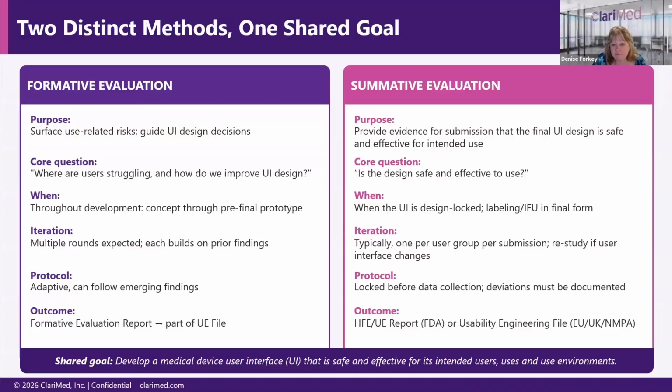So, there was a question in the Q&A. Is it required to have plans for both evaluation types? Yes, it is a requirement. Please go on, Denise. Yeah, so you're required to have a user interface evaluation plan, which can be pretty high level. You're not required to have an individual protocol for each formative. You are required to have a protocol for the summative.